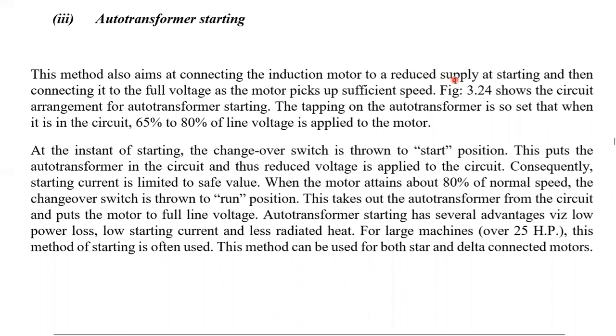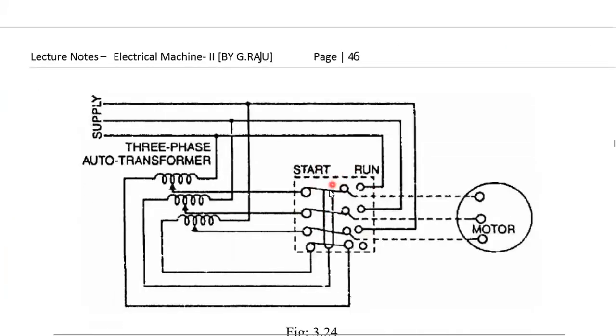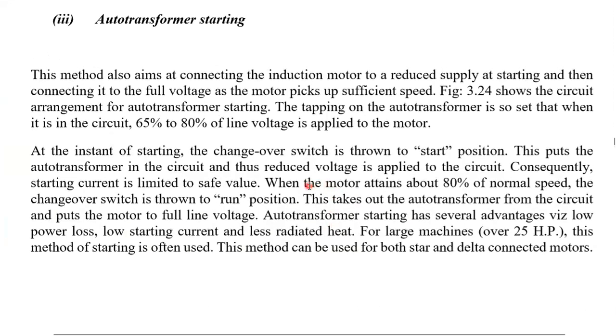This way, the induction motor torque and current can be controlled by applying the reduced voltage at starting, and then connecting to the full voltage when the motor picks up sufficient speed. At the time of starting, the reduced voltage is applied to the induction machine. When it picks up sufficient speed, the full voltage is applied. First, at the time of starting, the reduced voltage is applied, and then gradually the tappings are increased, and the output voltage increases by using the auto transformer. This shows the circuit arrangement of auto transformer starting. You can easily understand the concept by using the circuit diagram.